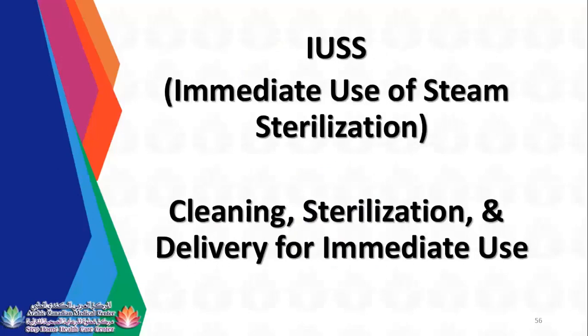IUSS, or immediate use steam sterilization, is actually used in CSSD, especially in emergency cases. You are not allowed to use IUSS just because you don't have enough instruments. You will just use immediate use steam sterilization if it is an emergency. There's an emergency procedure, or your doctor is performing a surgery and the instruments fell down, and you don't have any instruments to use. So they can use IUSS.